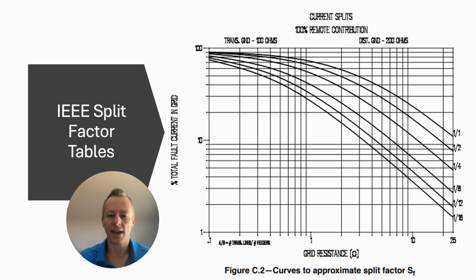IEEE Standard 80 has these split factor tables that are very helpful. You can model it in your software: incoming transmission lines, the actual neutral they return on, all the tower grounds and all the distribution lines, and you'll get a very calculated split factor because the software knows the grid resistance and all of those others. You can also use the IEEE split factor tables.